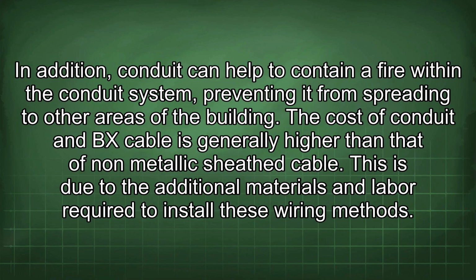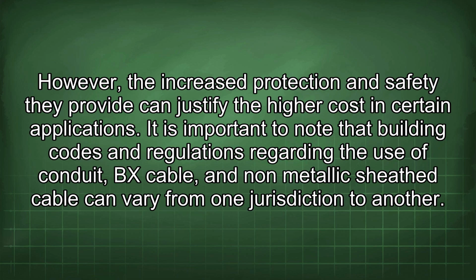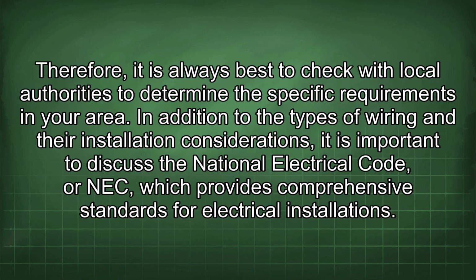In addition, conduit can help to contain a fire within the conduit system, preventing it from spreading to other areas of the building. The cost of conduit and BX cable is generally higher than that of non-metallic sheathed cable. This is due to the additional materials and labor required to install these wiring methods. However, the increased protection and safety they provide can justify the higher cost in certain applications. It is important to note that building codes and regulations regarding the use of conduit, BX cable, and non-metallic sheathed cable can vary from one jurisdiction to another. Therefore, it is always best to check with local authorities to determine the specific requirements in your area.